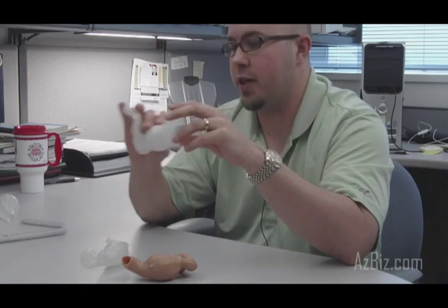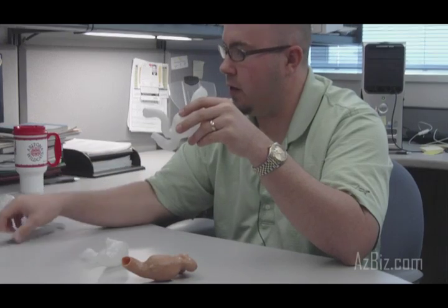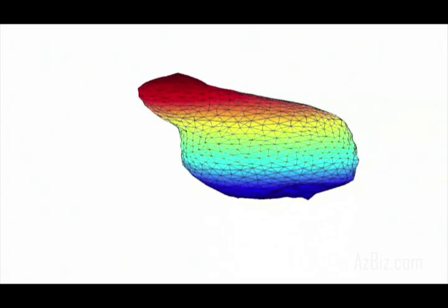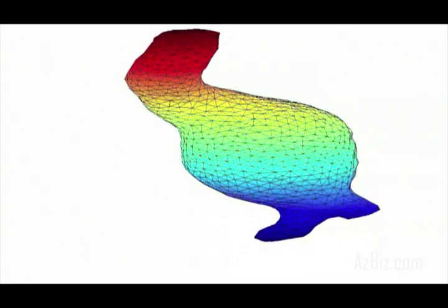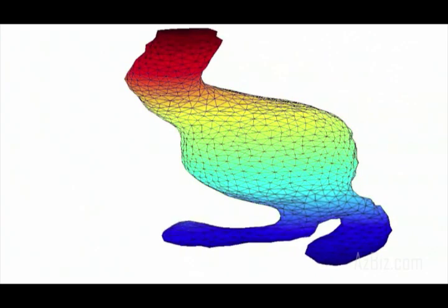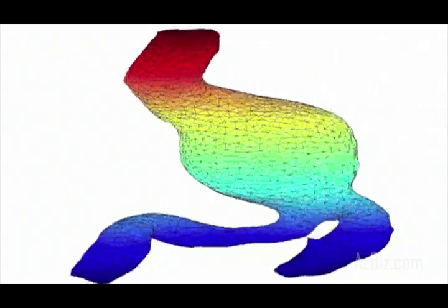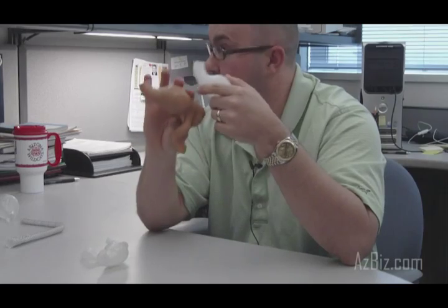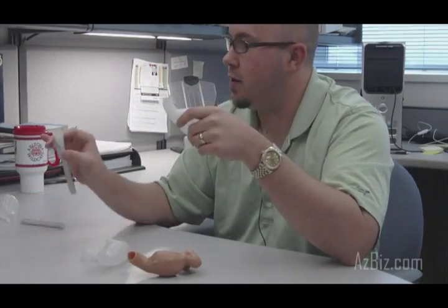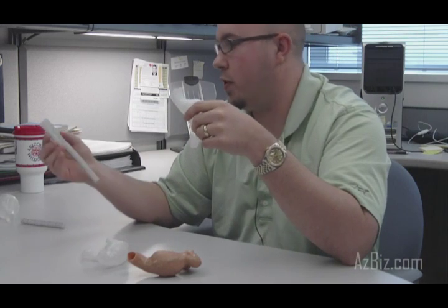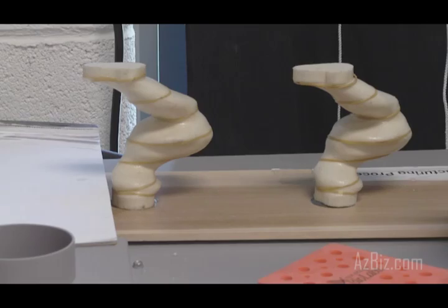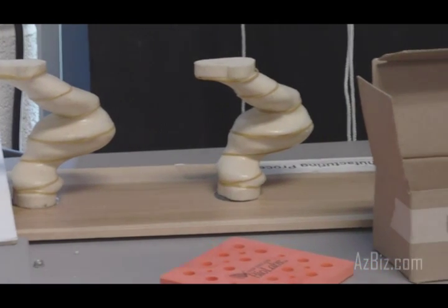Still, we would take this material, in this case because it's thermally sensitive, it becomes much more compliant at higher temperatures. So we'd heat it up, crimp it down, put it in the catheter, push it in, pull the sheath off, and then use a heated balloon or some other mechanism of heating, whether it be induction heating or otherwise, to thermal form this material into this aneurysm on the inside. In the same way that you're doing this, only this is temperature sensitive, but it's a different type of temperature sensitive material.